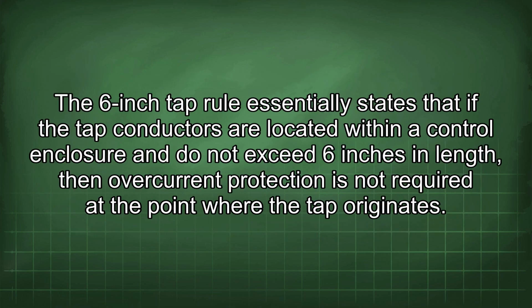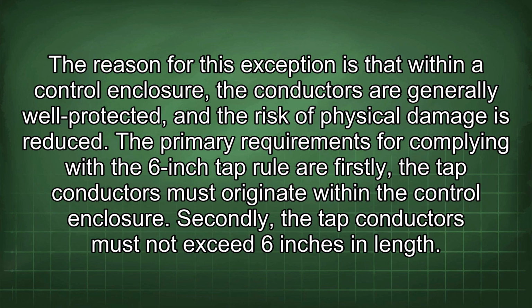The 6-inch tap rule essentially states that if the tap conductors are located within a control enclosure and do not exceed 6 inches in length, then overcurrent protection is not required at the point where the tap originates. The reason for this exception is that within a control enclosure, the conductors are generally well protected and the risk of physical damage is reduced.